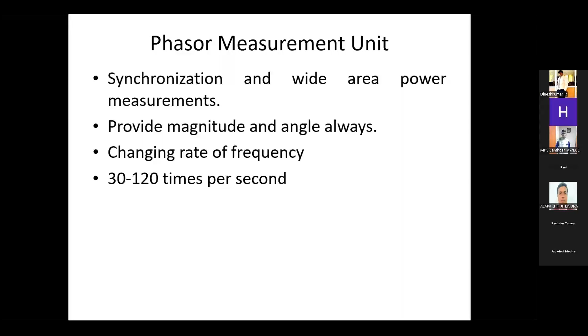Here we have a data comparison between SCADA and the phasor measurement unit. The phasor measurement unit measures data 30 times per second, so we get accurate information - like the disturbance in the voltage, the voltage magnitude - all this can be determined. It is better than SCADA.